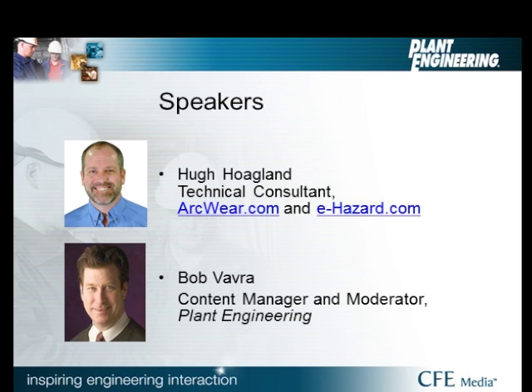As I said in the presentation, and we go into more detail in our training, we want to make sure you understand you only get arc-rated clothing for arc flash exposures. If you have flash fire and arc flash exposures, get something that is flash fire and arc flash rated, and you'll be in good shape. Just stay away from something that's generically claiming to be flame resistant. They often don't use the right standards, or in a few cases I've found companies that are actually just outright deceptive. It's very rare, but it has happened.